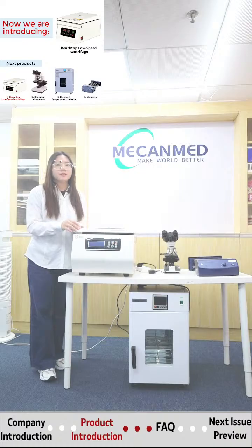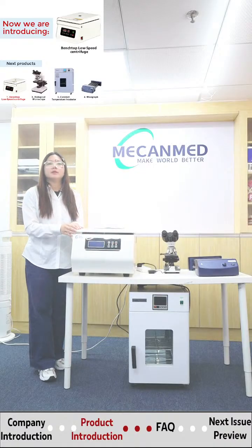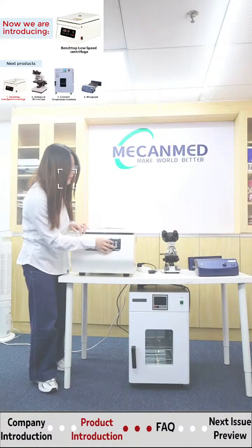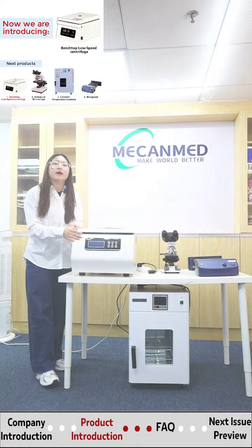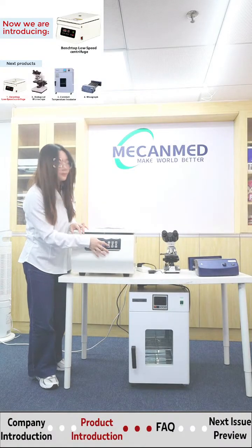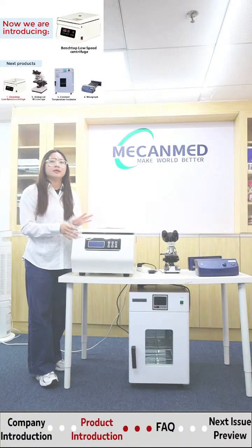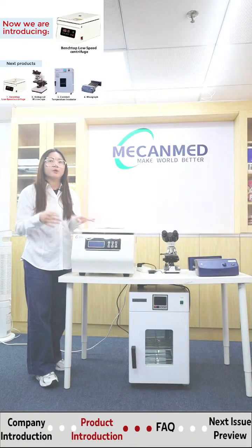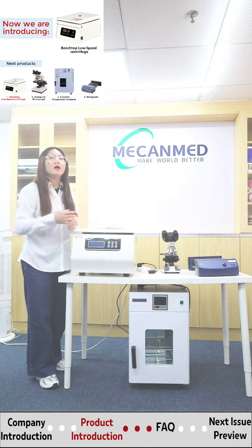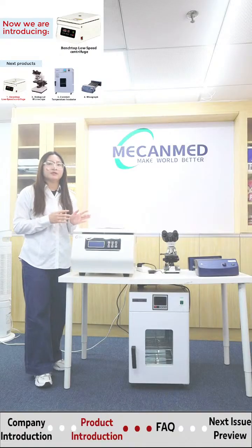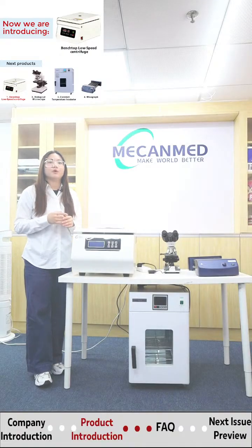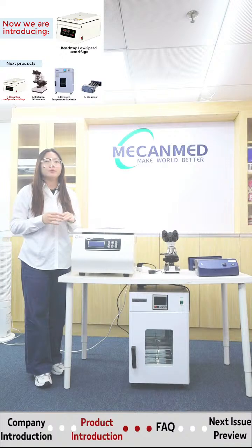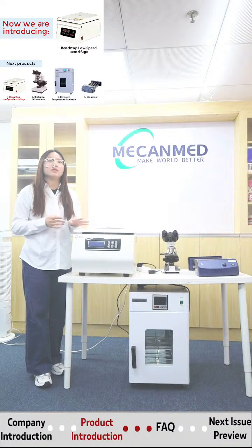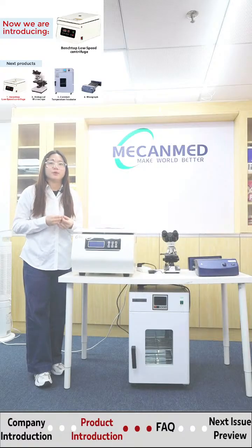Set the speed, RCF and time using the up and down buttons, and press the start button. Then the centrifuge will begin to run and you see the speed and time counting down on the digital display here. When it has completely stopped, the safety switch will allow you to open the door. Finally, carefully remove the samples. They are now separated and ready for the next step in your experiment.